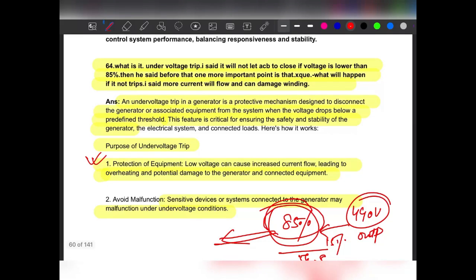Okay, so the main purpose of the under voltage relay, I already explained what it is and how it works. We continuously monitor the bus bar voltage or generator voltage. Let's suppose there is a set point, and if the voltage goes below the set point, and the setting is generally 85% of full load voltage, so if the voltage goes less than 85% of full load voltage for a few seconds, then it gives a signal to the relay, and the relay will isolate the circuit and trip the breaker. Okay, so that is the under voltage relay.